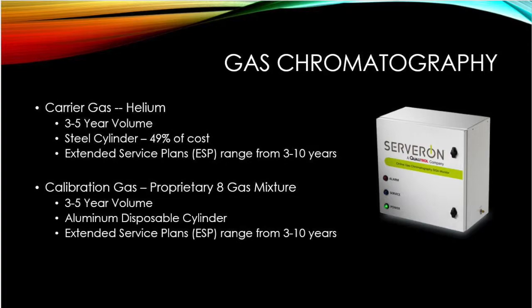Serveron sells extended service plans that range from 3 to 10 years, so that could cover either 2 or 3 helium cylinder replacements. There is an additional compressed gas that is used to calibrate the monitor. It's called calibration gas, which is a proprietary 8-gas mixture. It also has a 3 to 5 year volume. Those cylinders are aluminum disposable cylinders known as 2AL cylinders. And the extended service plans also range from 3 to 10 years for those as well.